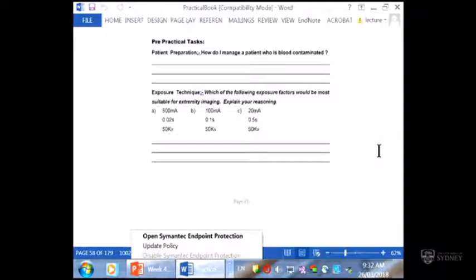So they're your options. Okay, this one's great because look at the short time. That's great for stopping movement. But the problem is 500 mA is broad focus. I've lost some image resolution. This one, well, it's fine focus. That's fine, but the time's too long. This one is just right. It's the biggest fine focus, so it's kept my time fairly short, and that's why.